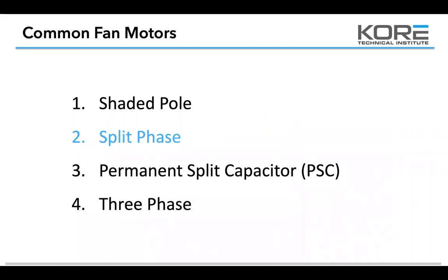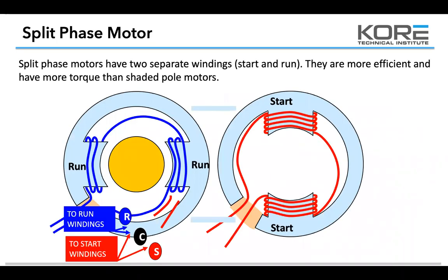Split phase. This is another really common motor we use. It's going to have a set of start windings and a set of run windings. When you pull the cap off, you'll see the two sets of windings inside there. It's going to energize the start windings, and usually a centrifugal switch takes out the start windings. As soon as that motor starts cranking up to a certain speed, there's what's called the centrifugal switch in there. As soon as the speed hits that centrifugal switch, the switch opens and de-energizes the start windings, and the start windings stay out of play until the motor slows down to a speed where it re-engages the centrifugal switch.